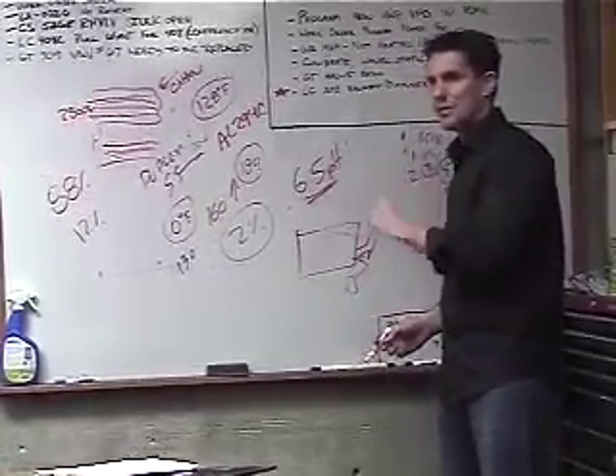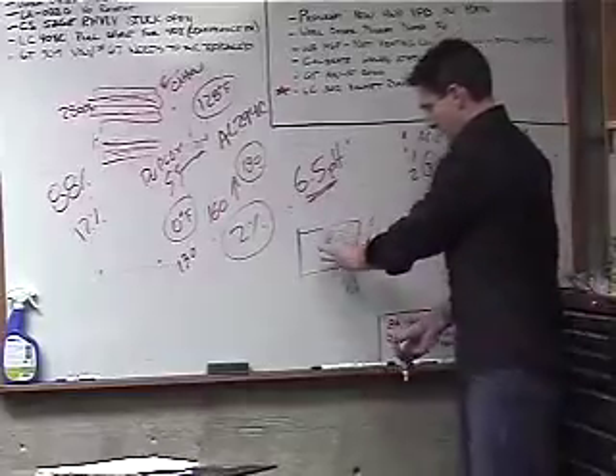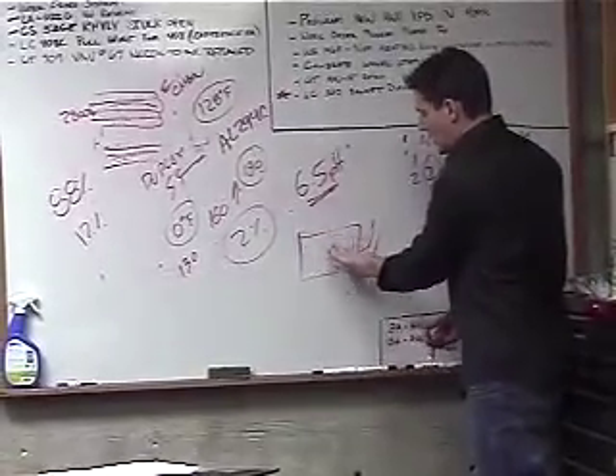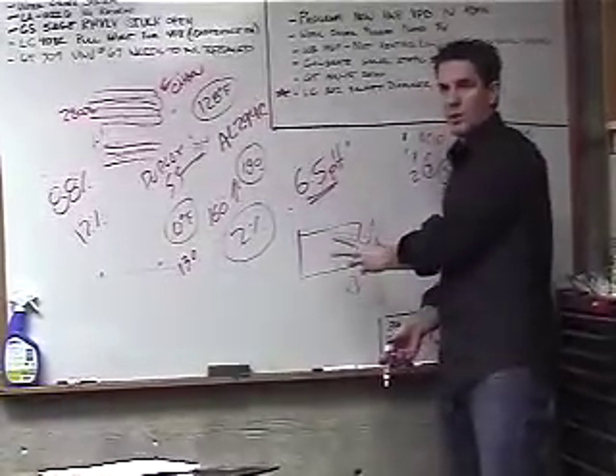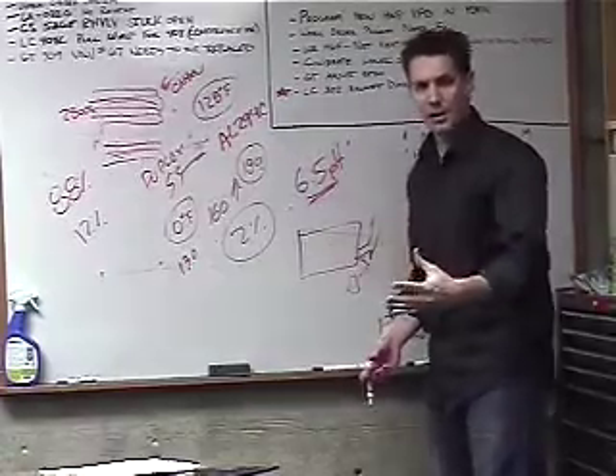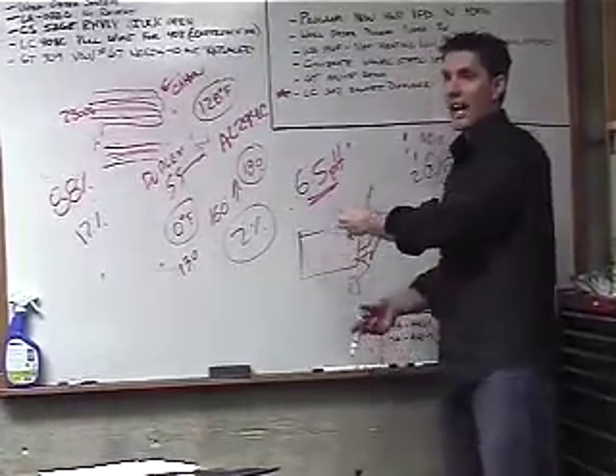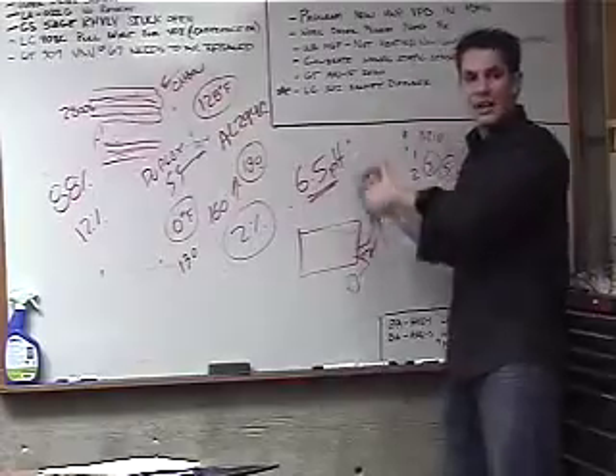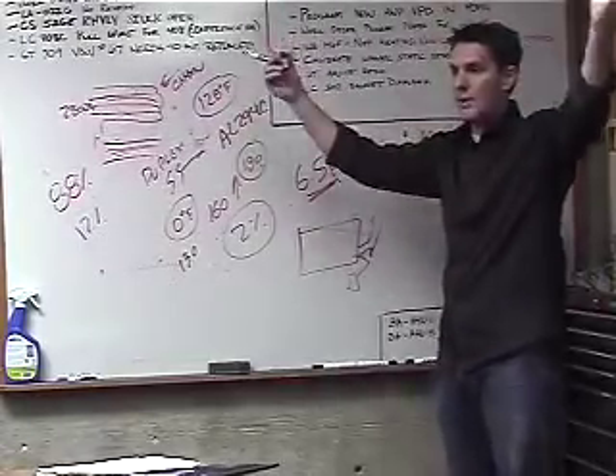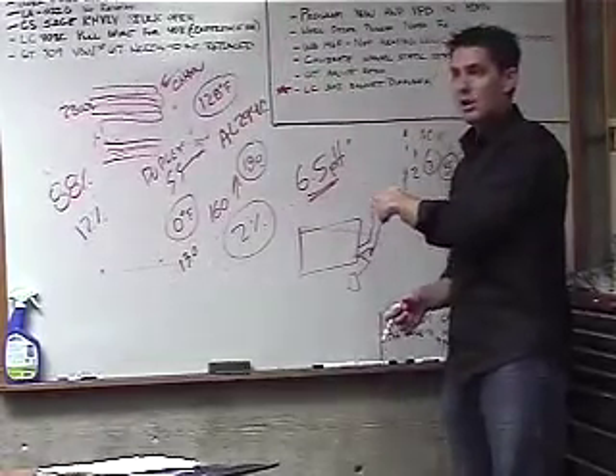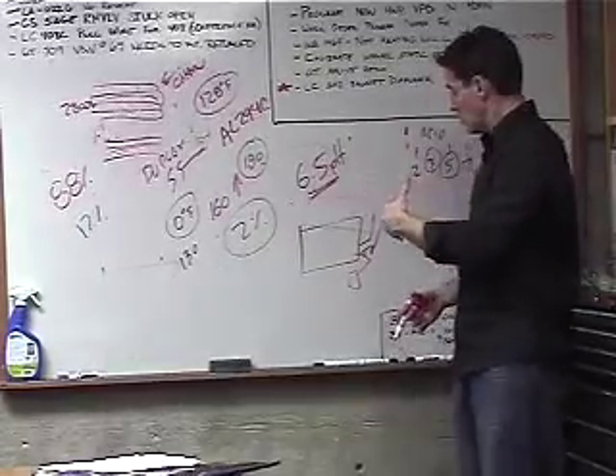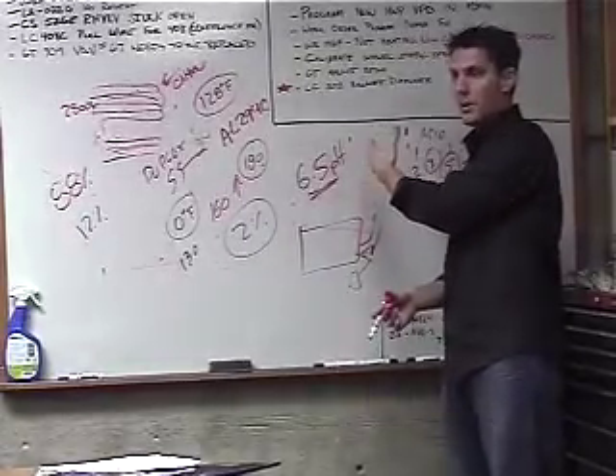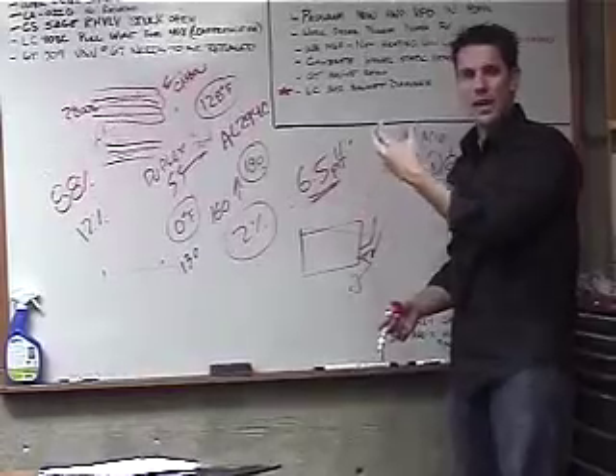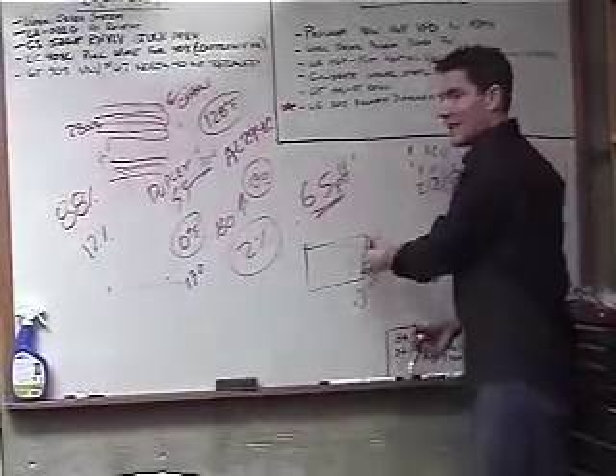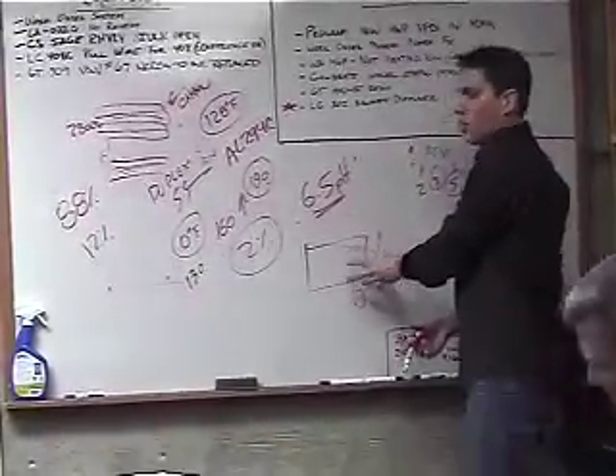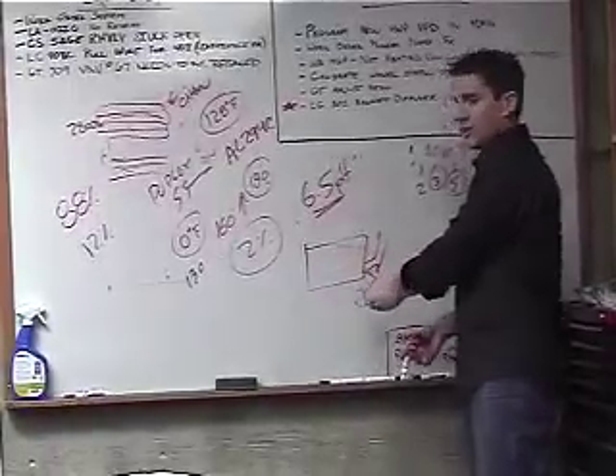That bucket is not to neutralize it. Again, what's happening is we had to create an opening at the bottom of this boiler so that we could get the condensate out. The flue gases, because they're hot, they're lighter than air, so they're going to go up the stack, and through chimney effect, they're going to go out to the atmosphere. But unfortunately, the steam was also going up, but it's not anymore because it's now turned heavy. It's turned into a liquid. So it's coming back down. So we have to basically punch a hole in everything, and we now have to run that to the drain.